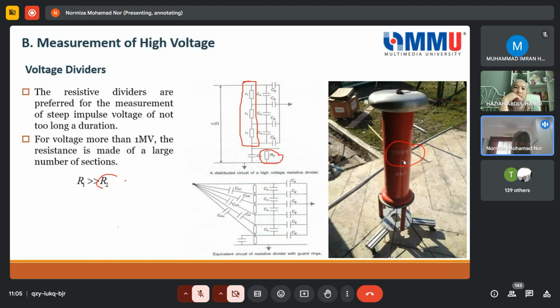Sorry, this one I did not put in here, but this one is actually because of the stray capacitance. When you have the resistance, you also subject your equipment to the stray capacitance and ground capacitance. This cannot be avoided, but it can be minimized by having this guard ring. The guard ring is like having capacitance all connected to one terminal point here. This is just part of the construction. So when you have this, you can minimize the stray and ground capacitance.